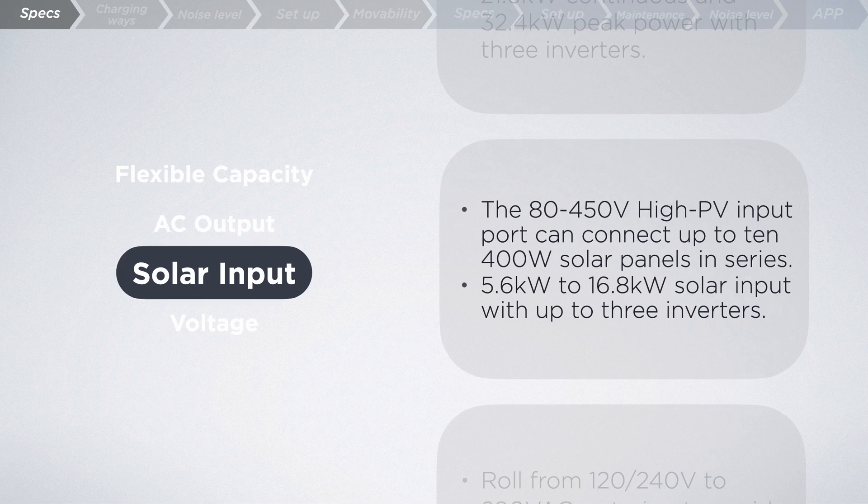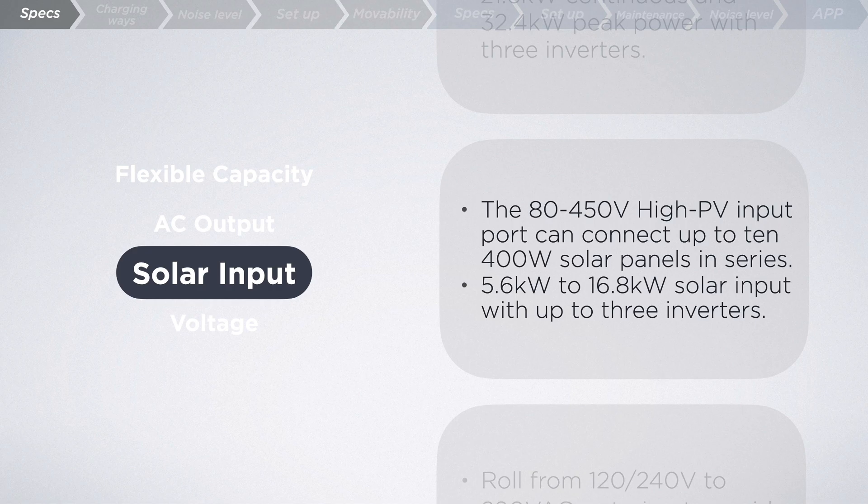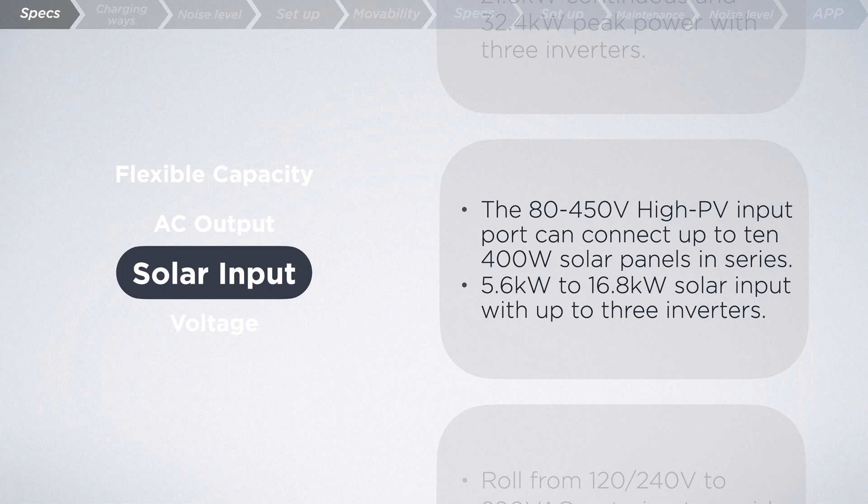Solar input? Check. The 80 to 450 volts high PV input port can connect up to 10 400-watt solar panels in series. If you're a sucker for solar energy, no worries. With up to 3 inverters in the system, it supports 5.6 kilowatts to 16.8 kilowatts solar input.